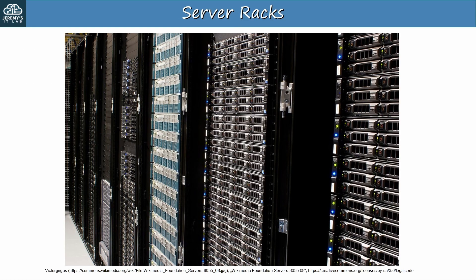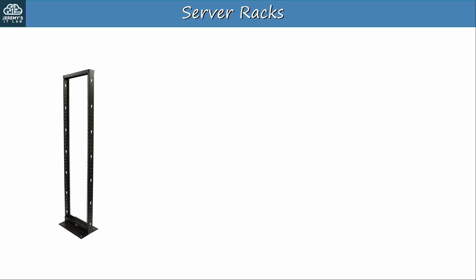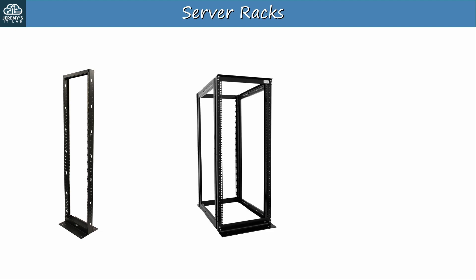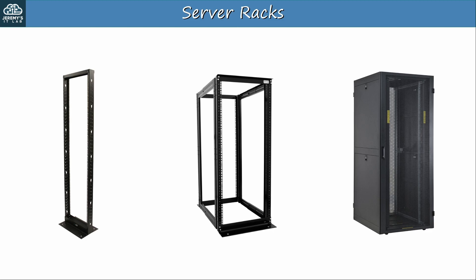So let's talk about server racks. Note that although the term server rack is commonly used, we don't just mount servers in them, but network devices too. However, the term server rack seems to be more common than network rack. The devices in this image are servers owned by the Wikimedia Foundation mounted in racks in a data center. There are a few different kinds of racks. Some companies might mount their devices in simple 2-post racks. Racks like this are often sufficient for smaller and lighter devices. Others might require 4-post racks, where some devices need to be attached to both the front and back posts depending on size and weight. For improved physical security, it's common for the rack to be enclosed in a locked cabinet. There are other types too, for example wall-mounted racks.